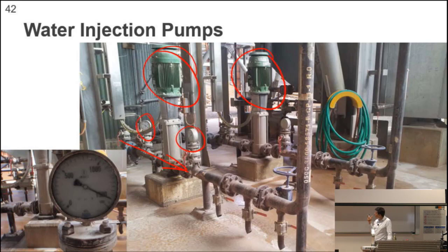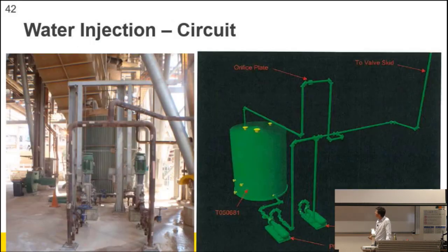So one of these is running all the time to give you continual pressure, and the pressure is about 1.45 megapascals. Grundfos six stage, anyway, whatever. Pumps, they're centrifugal, but they've got to go through multiple stages to create the pressure. This was the design spec, right?